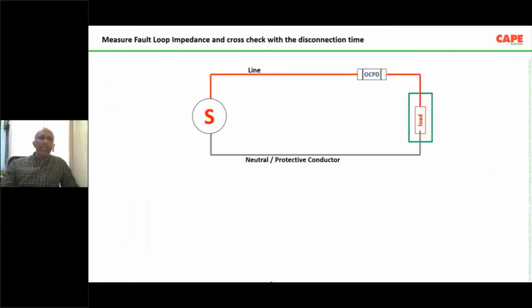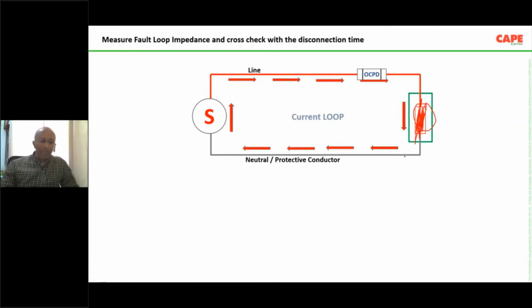Now, here you have a source, you have a load, and this is the fault. Imagine there is a fault in your load, there is some short circuit, or there is some earth fault, maybe in a UPS or maybe in a circuit. The fault current is flowing in this closed loop, starting from the transformer, coming through your protective device, and going back to the source.